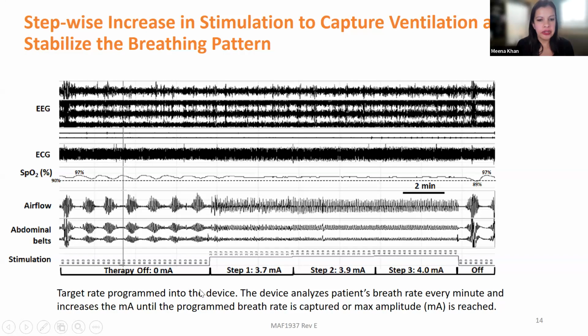Once the time has set and the therapy turns on, it analyzes the breathing and sees if the patient is at the target breath rate that's set into the device. If it's not, it will increase the milliamplitude, or the strength of stimulation, until it captures the breath rate that's been programmed into the device. Once it reaches that target milliamplitude, we call that capture, that they've captured their rate. And then you can see here where the therapy is turned off and the central apnea has come back.